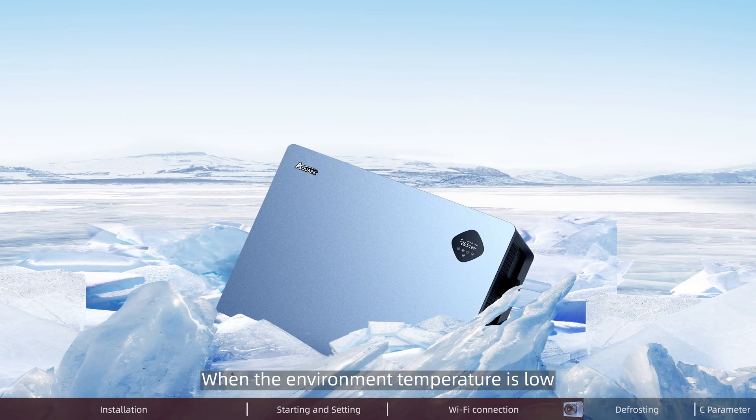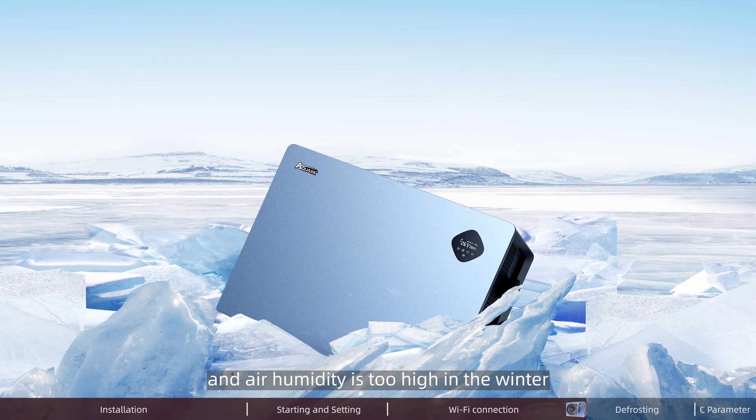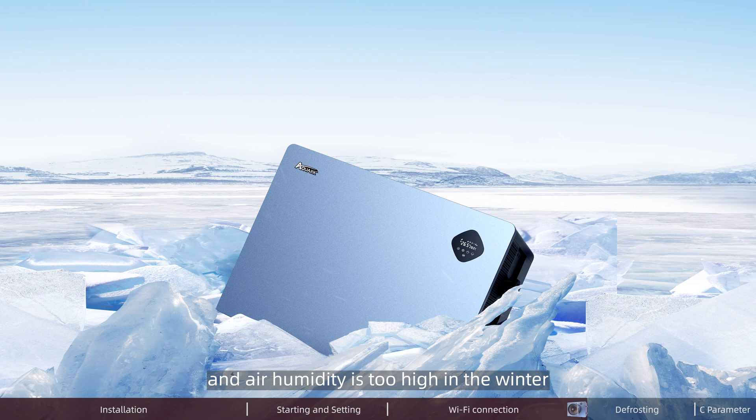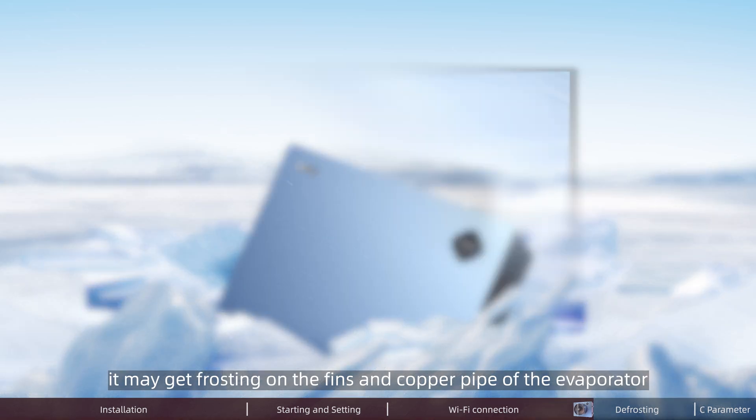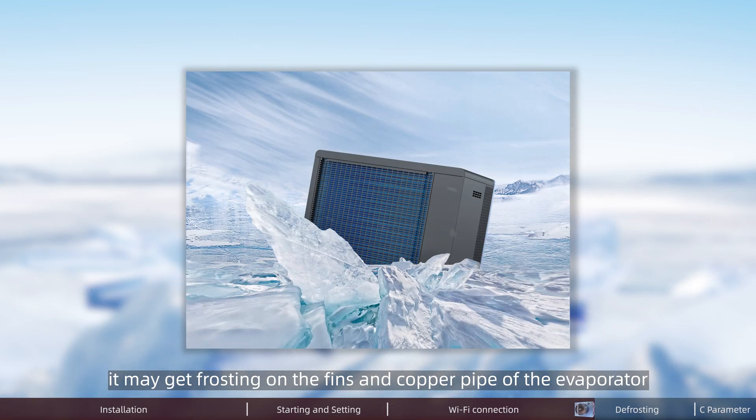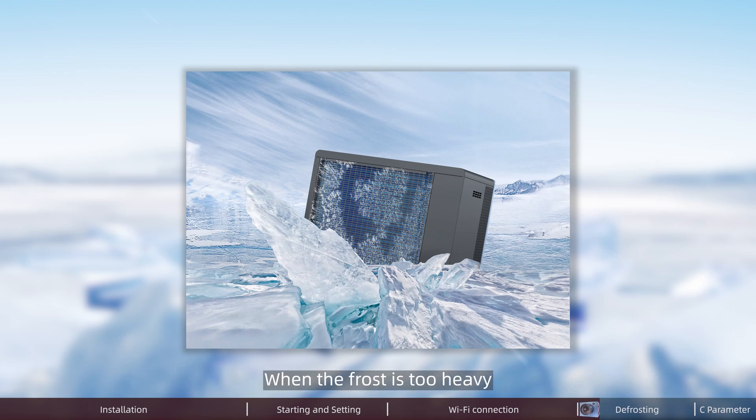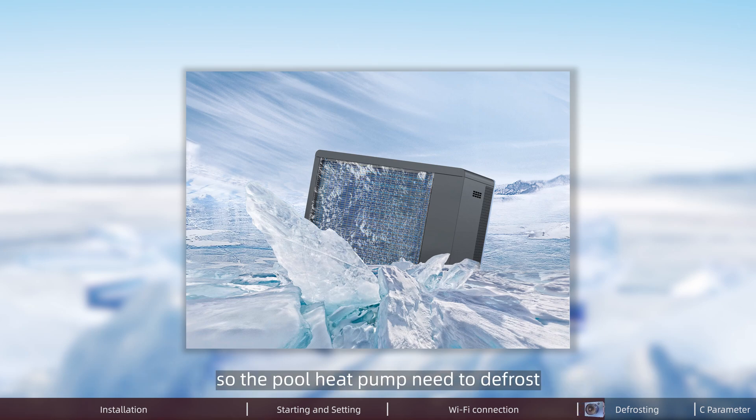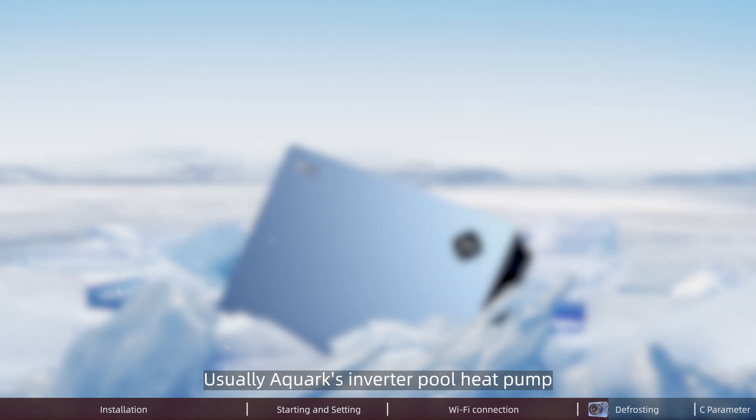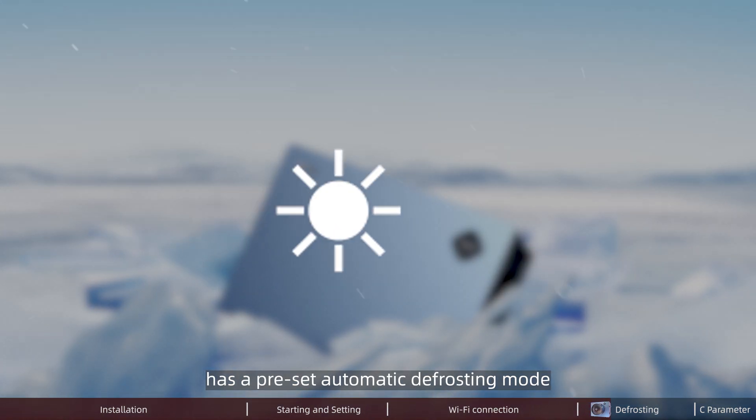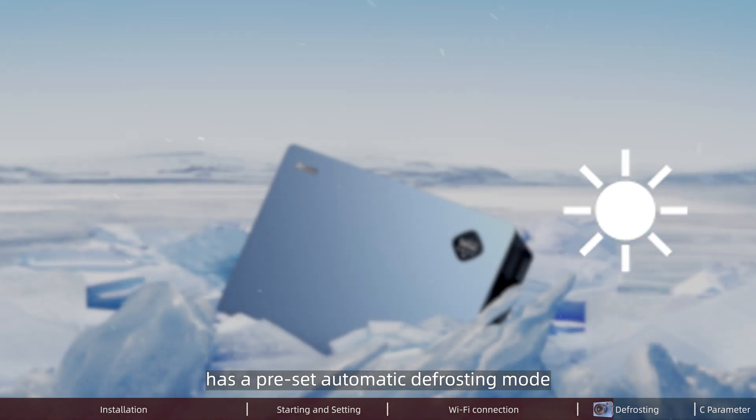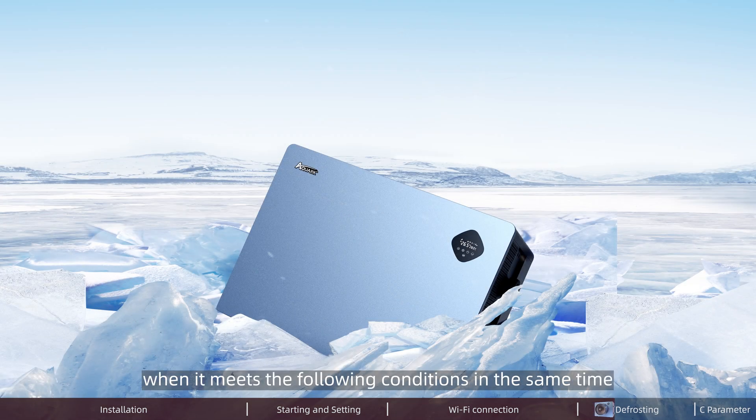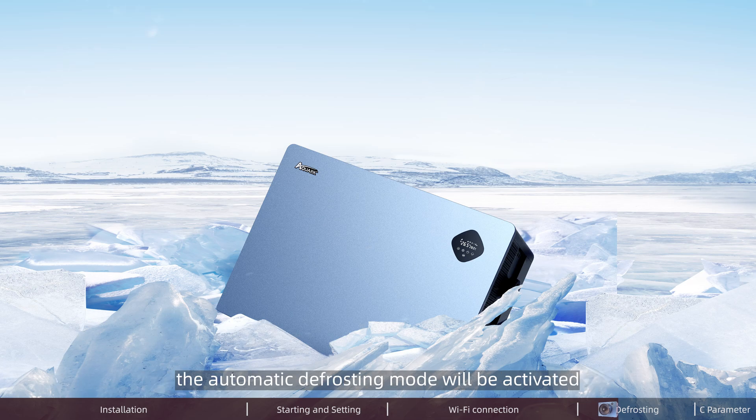When the environment temperature is low and air humidity is too high in winter, or when there is not enough space for air circulation, it may get frosting on the fins and copper pipes of the evaporator. When the frost is too heavy, it will affect the effect of heating, so the pool pump needs to defrost. Usually Aquark's inverter pool heat pump has a preset automatic defrosting mode. When it meets the following conditions at the same time, the automatic defrosting mode will be activated.